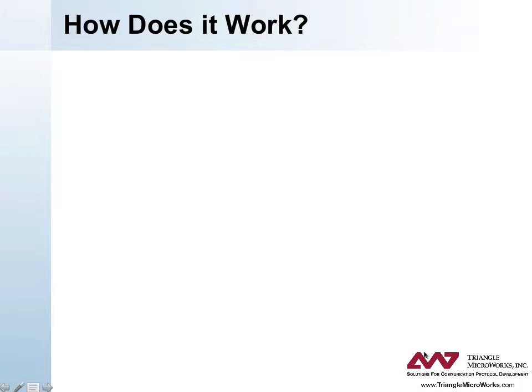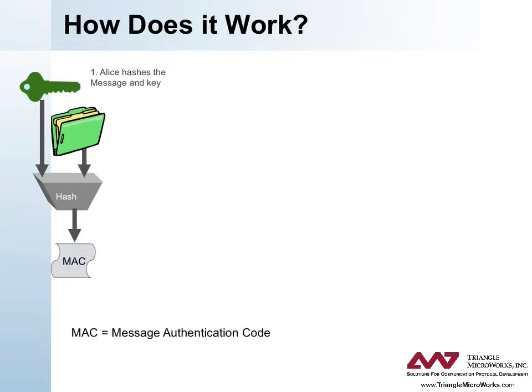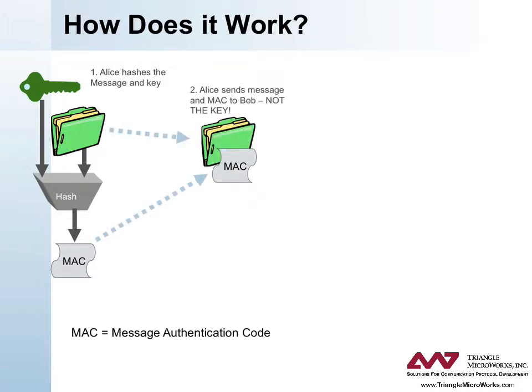Let's assume Alice is trying to send a message to Bob in a way that Bob can be sure the message is authentic. To make it work, Alice and Bob must have previously shared a key — a string of numbers like a password — that only the two of them know. Alice performs the hash function on the message she wants to send, concatenated with the key. This produces what is called a Message Authentication Code, or MAC. DNP3 SA V5 and later also support MAC calculation methods that are not technically hashes, but the effect is the same. Alice sends the original message and the MAC value to Bob. She does not send the key, because it could be seen by an attacker. However, the message is not encrypted in this case. The attacker can see what the message is doing, but cannot modify it or send a false message of the attacker's own.